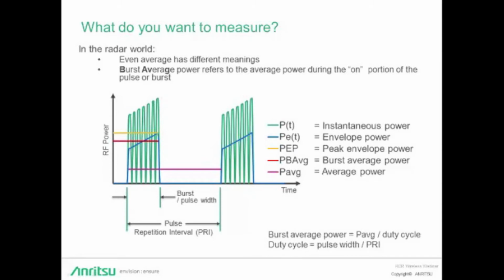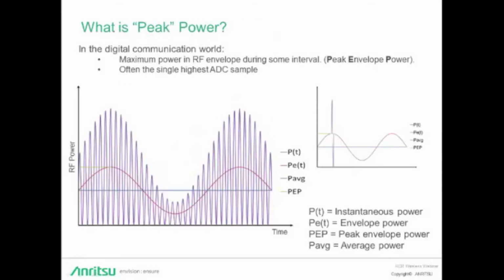Now, if the pulse is well behaved and the pulse width or PRI are known, an RMS detector can be used to calculate the burst average power by factoring in the duty cycle of the measurement, which you can see in the equations at the bottom of the slide. So here the diagram shows the various types of RF power measurements you might want to compare and think about. A second ago we talked about well-behaved waveforms. If a pulse is not well behaved, and/or if you have other types of modulation in the signal, like in the digital communications world, an average or RMS sensor may no longer be sufficient. Similar to the pulse signal case we just discussed, it's unlikely one would want to measure the instantaneous power. Instead, they're probably more interested in the envelope power.